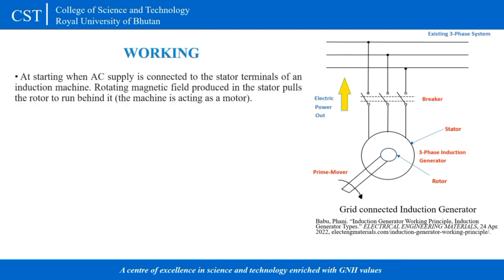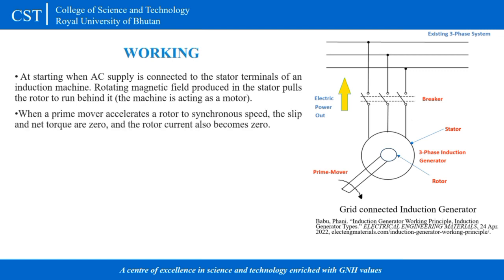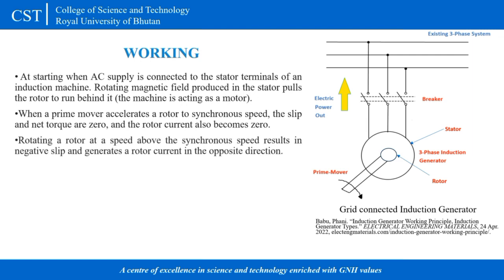At starting, when AC supply is connected to the stator terminals, a rotating magnetic field is produced in the stator that pulls the rotor to run behind it. When a prime mover accelerates the rotor to synchronous speed, the slip and induced torque become zero and the rotor current also becomes zero. Rotating the rotor above synchronous speed results in negative slip and generates a rotor current in the opposite direction.